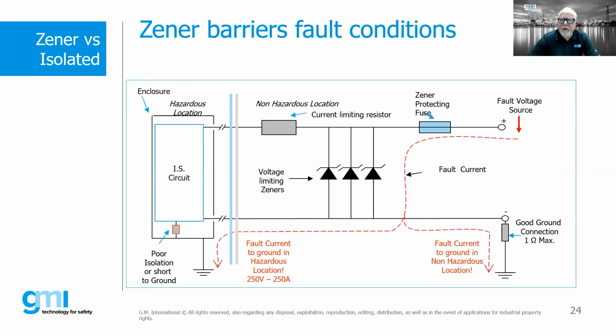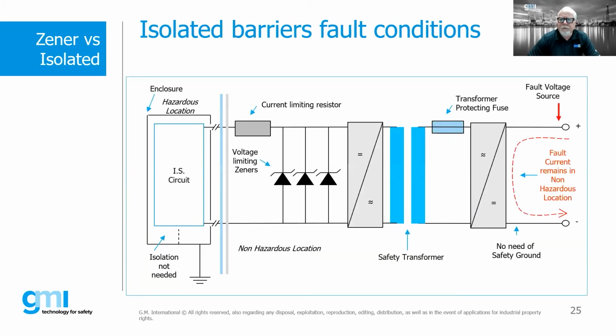So a Zener barrier in a fault condition, right? We have a fault condition like what we showed before. Again, we have that fault condition to ground in a non-hazardous area, but potentially we could have that fault condition to ground in a hazardous area. So this is the important reason why we want to make sure that we do have a good ground, right? We don't want to have it tied into our normal ground, but we want to make sure that we do have a good, clean earth to tie it to that's separate from our normal dirty earth, if you will. And again, in this particular situation, our IS circuit, the isolation is not required. We don't have that requirement for the safety ground.